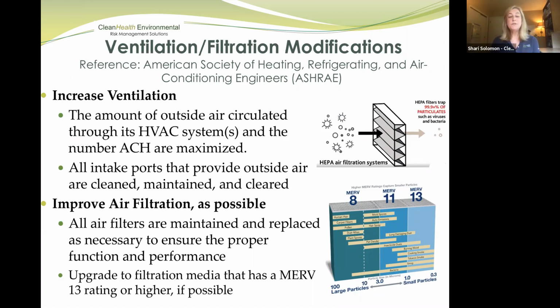All intake ports are provided. Outside air intakes are cleaned, maintained, and cleared. So again, part of your increasing ventilation. And then the other component is improving air filtration. Changing out your filters per manufacturer's instructions, doing your inspections to make sure you have optimal performance and function of your systems, and upgrading filtration to a MERV 13 rating if possible, or higher if possible.